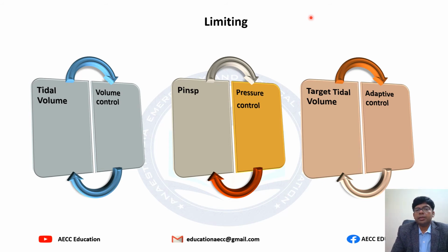When the set limit is reached, a ventilator stops delivering further gas into the circuit. Reaching the limit does not mean the immediate cycling from inspiration to expiration.